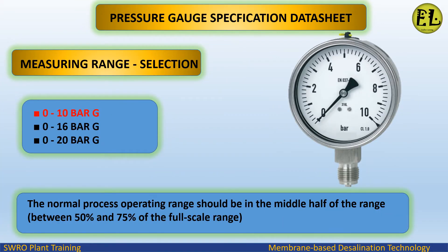Measuring range selection. Available ranges are 0 to 10 bar G, 0 to 16 bar G, and 0 to 20 bar G. The normal process operating range should be in the middle half of the range, between 50% and 75% of the full scale range. We select 0 to 10 bar G for this application.